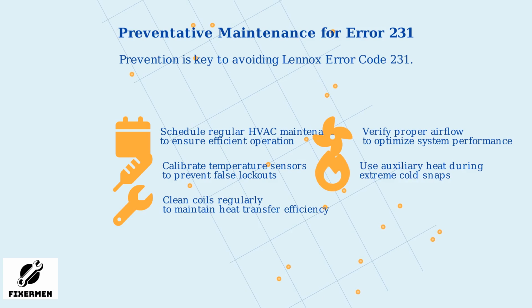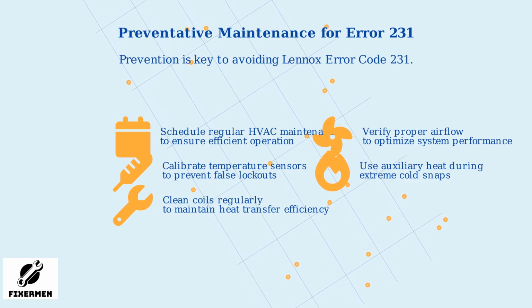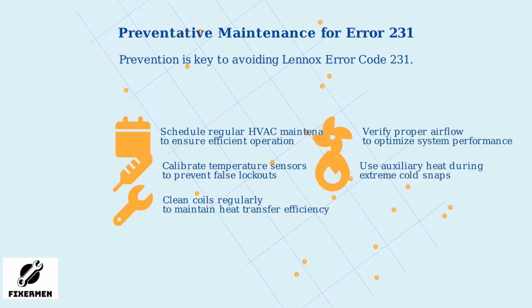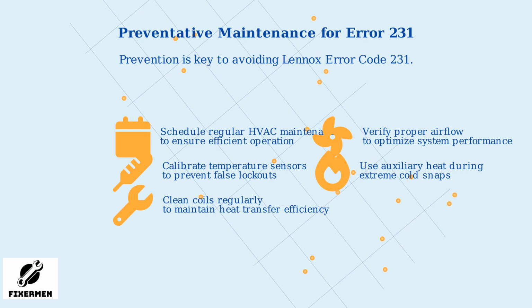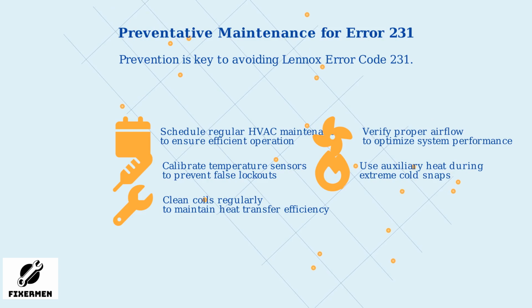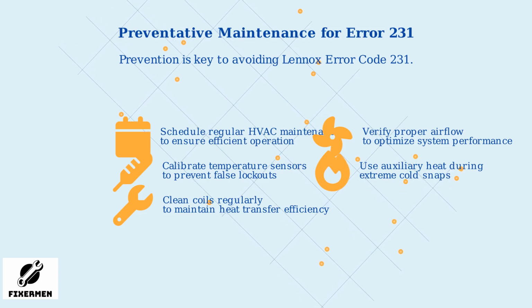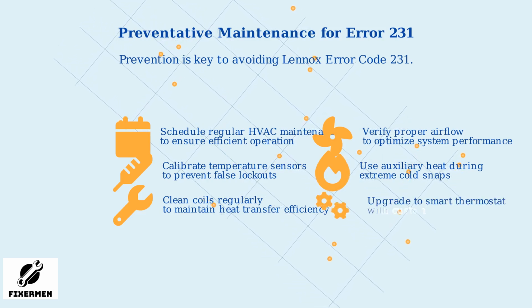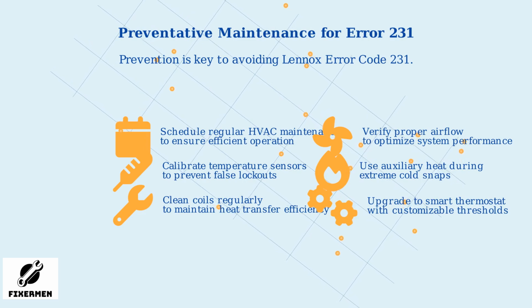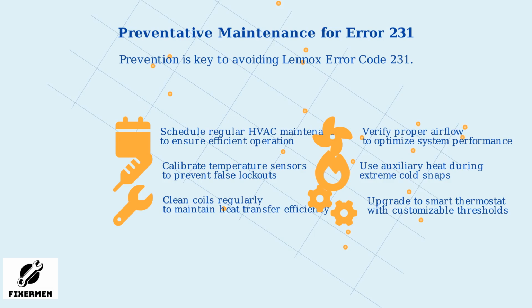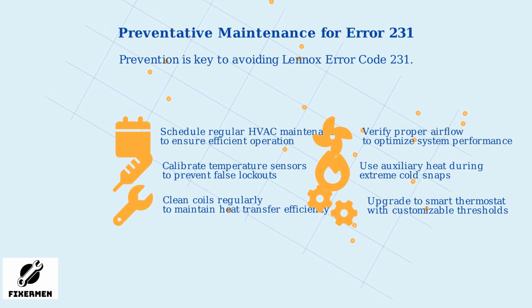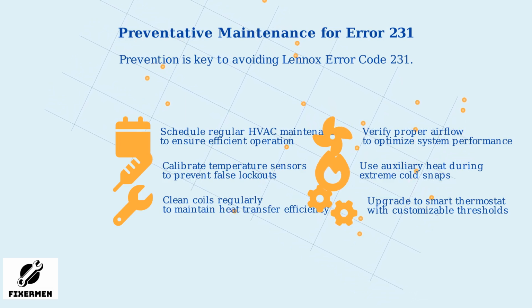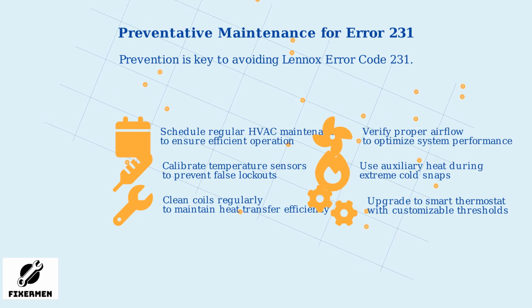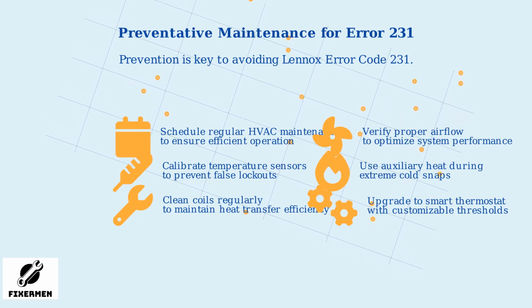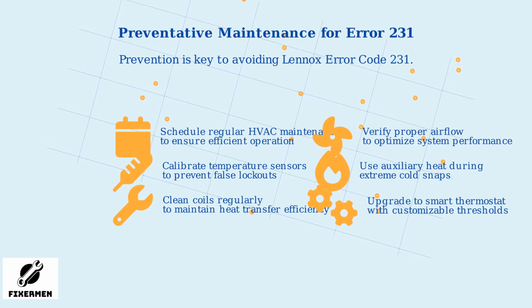During extreme cold snaps, consider using auxiliary heat sources like electric resistance heat to supplement your heat pump. This reduces strain on the primary system and helps prevent low ambient lockouts. Upgrading to a smart thermostat with customizable lockout thresholds can also significantly reduce the chances of encountering Error 231. These devices allow you to adjust settings based on your specific climate and usage patterns.